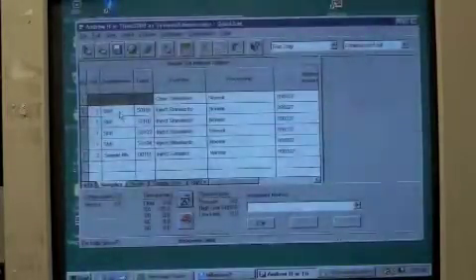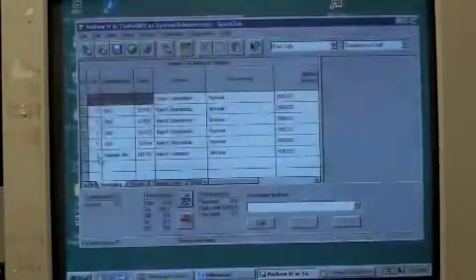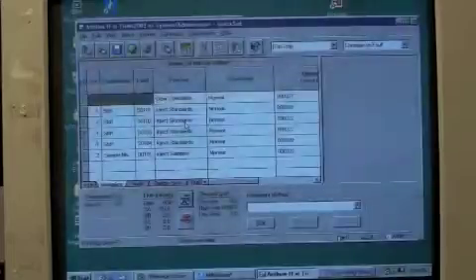This is giving us a summary, and I'm very happy with all that we've done so far, so let's go finish. As you can see now, it's already built a method for us. It's indicated the standard number here — standard number one. If we'd had two injections, it would have made that a two. At the end of it, it's placed our sample. All you've got to do now is press the green button, and you've successfully built a method and a sample set for HPLC.